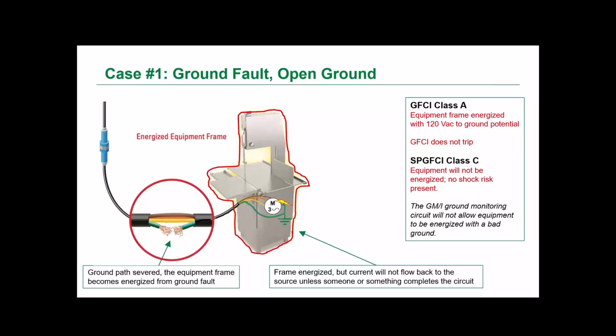So in this first case, you can see we have a ground fault present in the motor on the saw, and in that red circle, you can also see that the grounding conductor has been severed. So with the Class A GFCI, as we've discussed, when power is applied to the saw, it could run and appear to be working fine. But that ground fault has energized the frame of the equipment to line to ground voltage, and the GFCI is not able to see that or trip because there's no ground fault current flowing due to that broken ground.